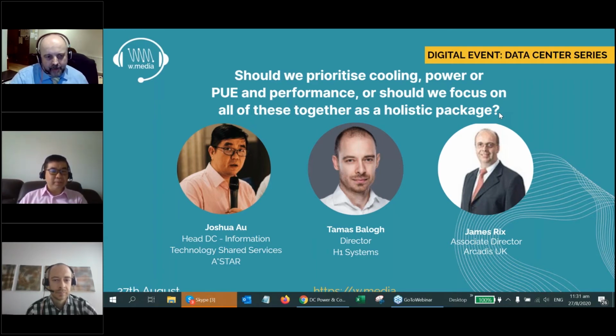As always, with PUE it's often down to how accurate it is and where you measure it within the system. But we also need to consider other things such as WUE, water being a very important component, which quite frankly at the moment is quite badly managed or measured within data centers.